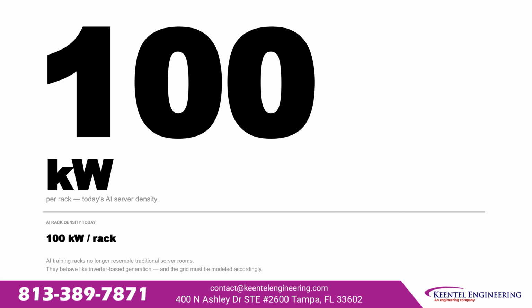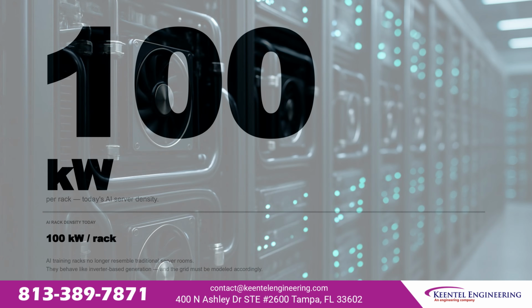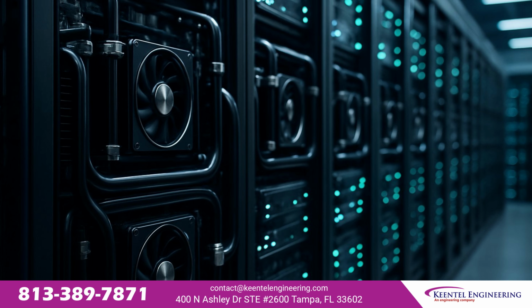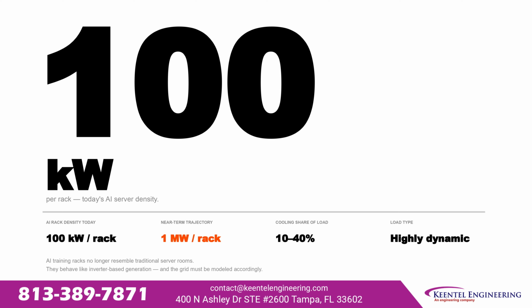Today's AI server racks draw 100 kilowatts per rack. Near-term trajectory, 1 megawatt per rack. Cooling accounts for 10 to 40% of total load, and the load type is highly dynamic. AI training racks no longer resemble traditional server rooms. They behave like inverter-based generation, ramping hard, cycling on training batches, creating grid-visible oscillations that conventional models don't see. The grid must be modeled accordingly.